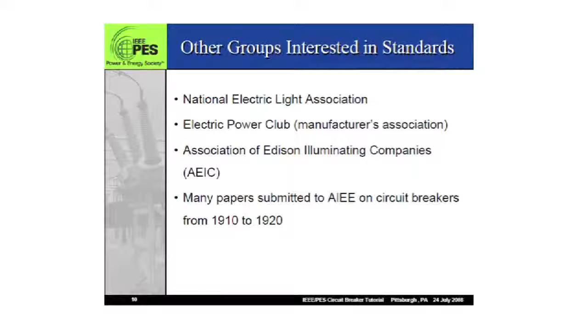These are some of the slides. In 1919, a club was formed in electric power, and in that club they decided that the breaker must be able to make two open operations with two minute intervals — no limit on flame or oil rejected. It doesn't matter, it can burn as long as it interrupts twice. Beautiful, I love it, just interrupt. This is how far we went with the technology. It's amazing — now we have 100 short circuit interruptions and people complain it's not enough.